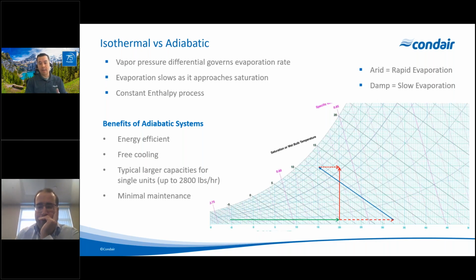If you don't need that cooling effect, it needs to be offset with supplemental heating, either preheat or reheat. But depending on the size of the system and the evaporation load, it may still be more efficient to do humidification or cooling with an adiabatic system compared to a traditional isothermal one.